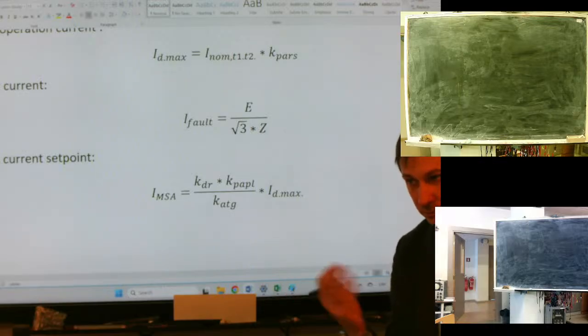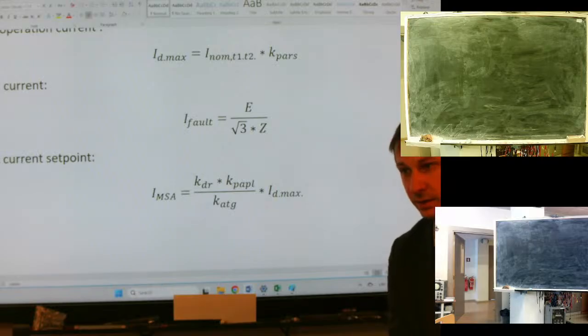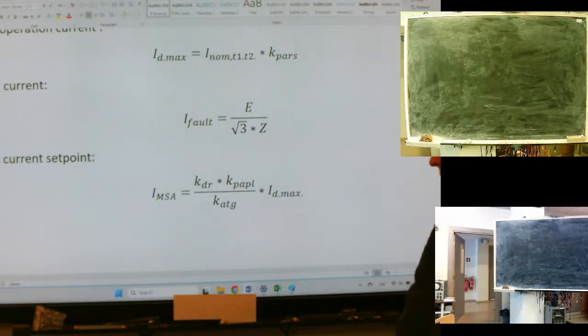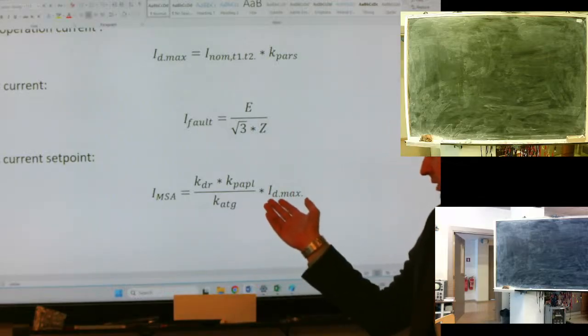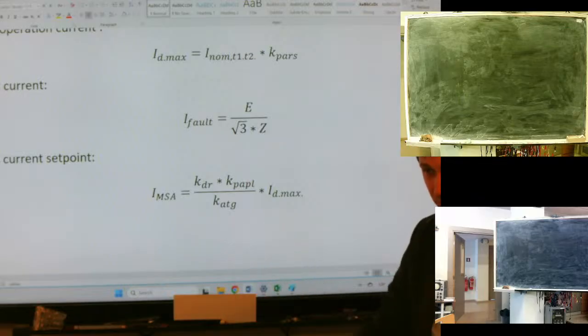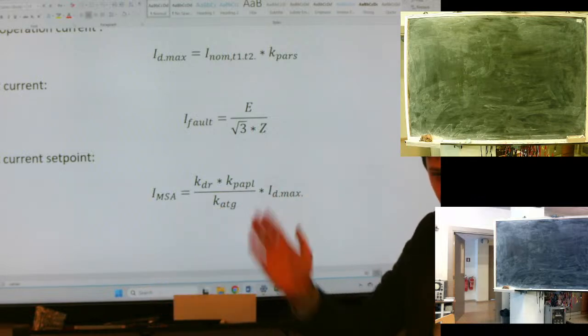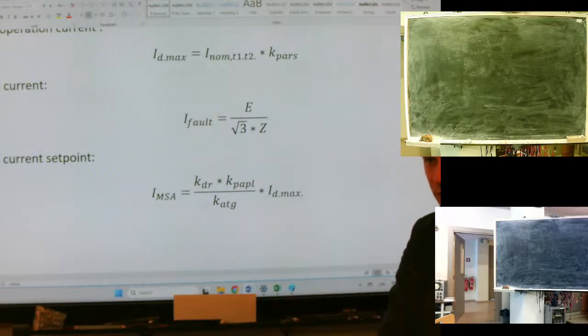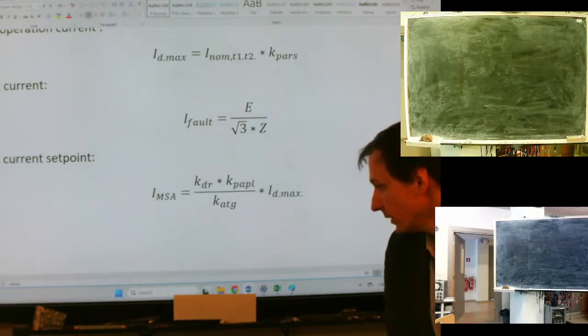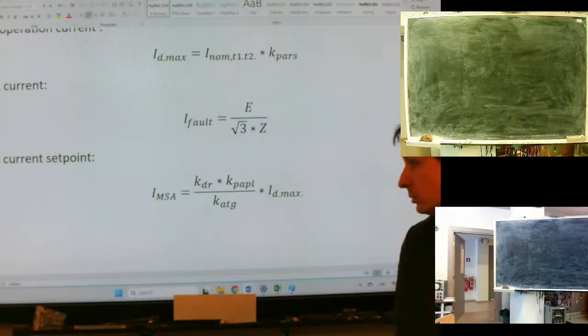But how we evaluate? Okay, sensitivity is very simple formula, so we need to divide our fault current by the set point, and we will have this coefficient, so 1.5. So 150 divided by 100, 1.5. But is it good? Good enough. How could we evaluate it? Okay, yes. So we need any tool to understand. So this is not as simple.